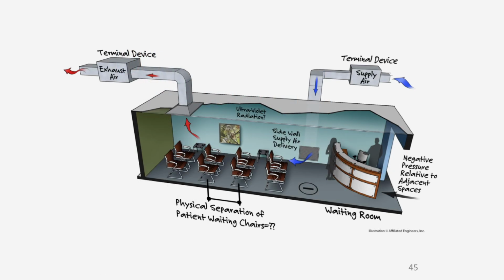And if we look at slide 45, where we've got a waiting area with some physical separation, and you deliver air low and blow it across that waiting room, it will lift and get out of the breathing zone very quickly and get exhausted or returned through HEPA filters. This is an effective way, I feel, of delivering air to waiting areas so that you don't have to shove the air down only to go back up again or to return the air low. But yet it keeps the air longer in the breathing zone. So displacement ventilation has great potential for lifting air in the waiting rooms, in atriums.